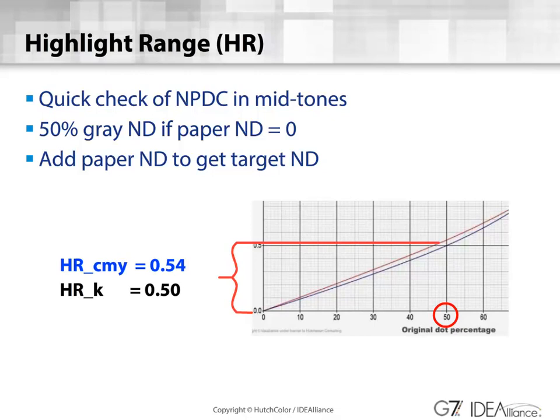In other words, if you want to test a printed sheet or a proof, you can quickly measure the neutral density of the paper. Let's say it's 0.05. Add that value to these two numbers you see here, so the 0.54 would become 0.59, and then measure that middle gray patch. And if the 3-color CMY HR patch is 0.59, then it's reading exactly right. If the paper was 0.05, add that to 0.50 for the black, you'd have a target value of 0.55. Measure a black 50% patch on the print. If it reads 0.55, then that's correct.